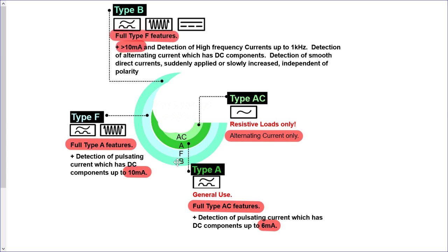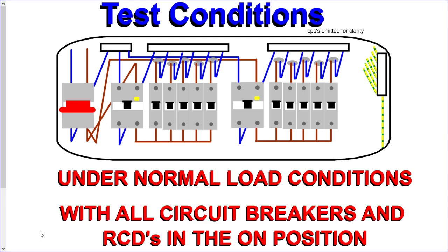But irrespective of the RCD type, obviously the information we've just looked at is about the DC measurements. We need to be aware that each RCD, we're dealing with a maximum leakage of 30% of its trip rating. So if that's a 30 milliamp RCD, that we've got here for the type A, then that would be 9 milliamps max leakage. All right. So how do we carry out this test?